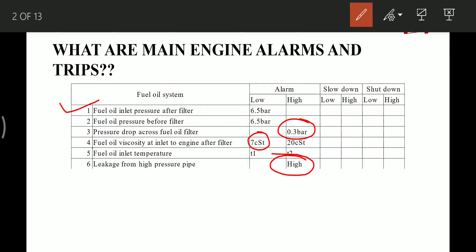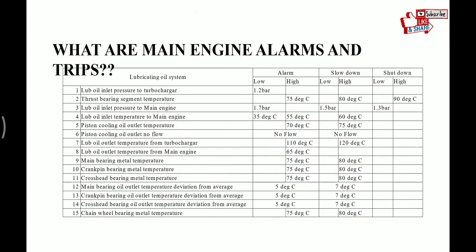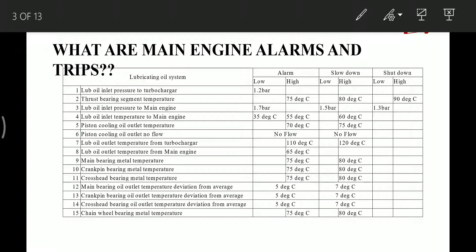The next system is the lube oil system, which has plenty of alarms. The first is lube oil inlet pressure to the turbocharger — it gives a low alarm at 1.2 bar. If pressure falls below 1.2 bar, it gives an alarm.